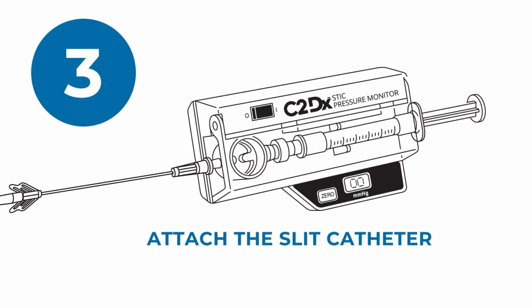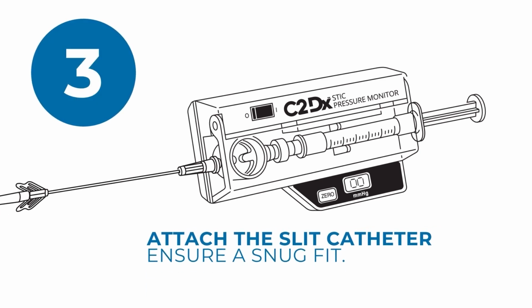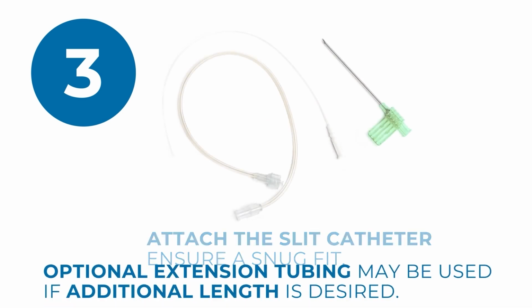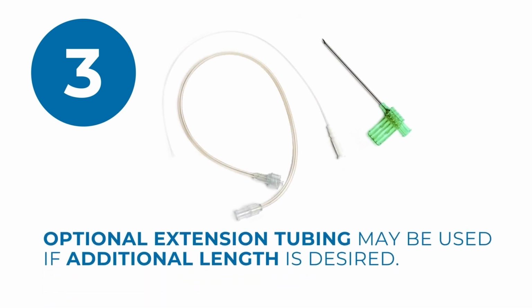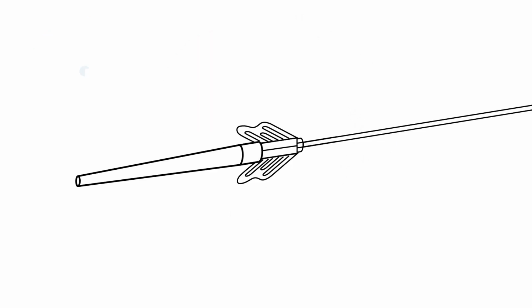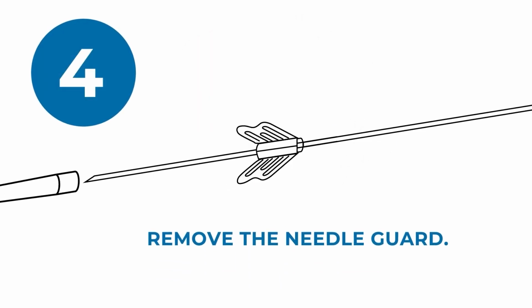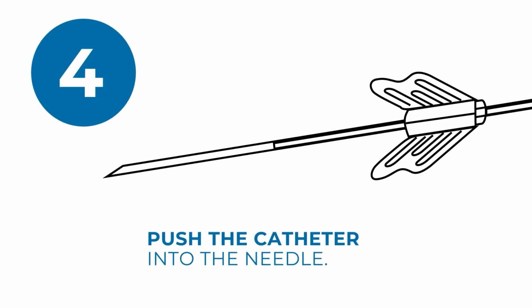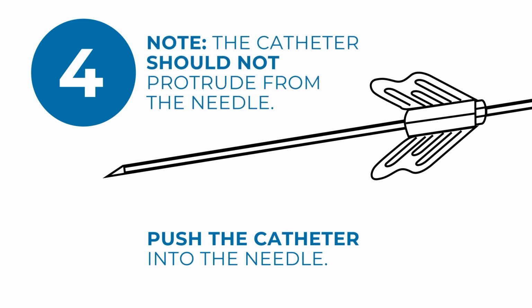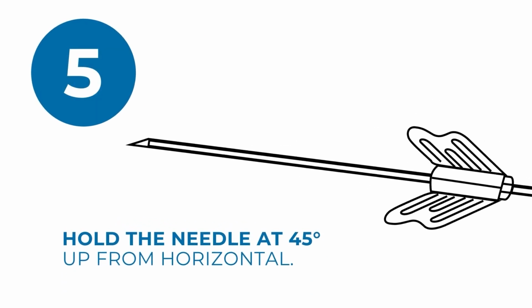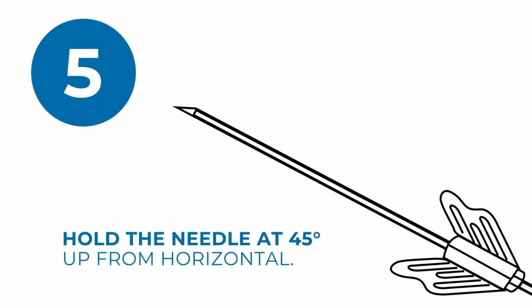Attach the slit catheter to the tapered chamber stem and ensure a snug fit. Optional extension tubing may be used between the slit catheter and the monitor if desired. Now, remove the needle guard from the breakaway needle and push the catheter into the needle until it is flush with the bevel of the needle. Note: the catheter should not protrude from the needle. Hold the needle approximately 45 degrees up from horizontal and slowly force fluid through the disposable to remove air.